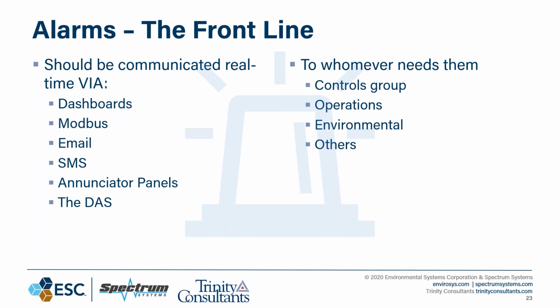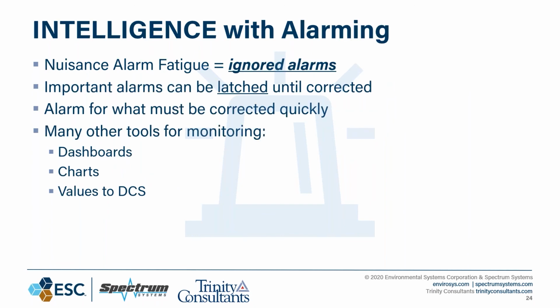pumping alarm indicators to annunciator panels in the control room, the front end of the DAS itself, and these can be pumped to whoever needs them, whether we're talking about your controls group, your operations group, environmental folks, anybody else who has skin in this DAS, keeping an eye on it. You can get alarms for these things at will when you want them, sometimes even when you don't. And that's when you need to employ some intelligence with the alarming. Let me repeat that, intelligence with alarming. Because if you have an alarm that just pops up, drives you crazy all the time, we call that nuisance alarm fatigue. And when that occurs, that generally becomes an alarm that people tend to ignore.